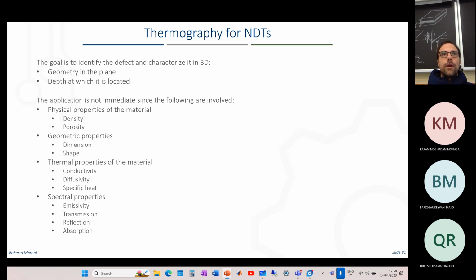So if you open a camera, there's a data sheet that gives you the operating range, and so the corresponding wavelengths that your camera is able to detect. So it depends, because, for example, in quality control, you can be interested in an operating range between 0 Celsius degrees and 100 Celsius degrees. Okay, but there are many other applications where you want to see higher temperature, 1,000, 2,000 degrees, and you can move to shorter wavelengths.